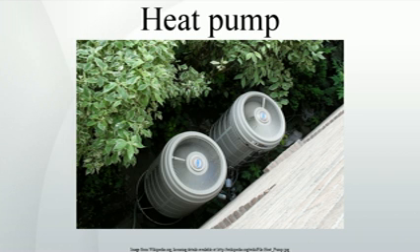Heat transport. Heat is typically transported through engineered heating or cooling systems by using a flowing gas or liquid. Air is sometimes used, but quickly becomes impractical under many circumstances because it requires large ducts to transfer relatively small amounts of heat. In systems using refrigerant, this working fluid can also be used to transport heat a considerable distance, though this can become impractical because of increased risk of expensive refrigerant leakage. When large amounts of heat are to be transported, water is typically used, often supplemented with antifreeze, corrosion inhibitors, and other additives.